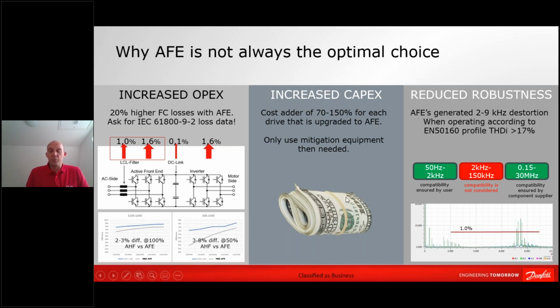The second part is, of course, that it's fairly expensive. AFE drives normally cost around 0.7, 0.8, 0.9 more than a standard drive. So you're typically paying double the price for an AFE drive compared to a standard drive. So if you're not needing mitigation, don't consider adding an AFE just for safety reasons. It doesn't give you anything. It's just a waste of money.